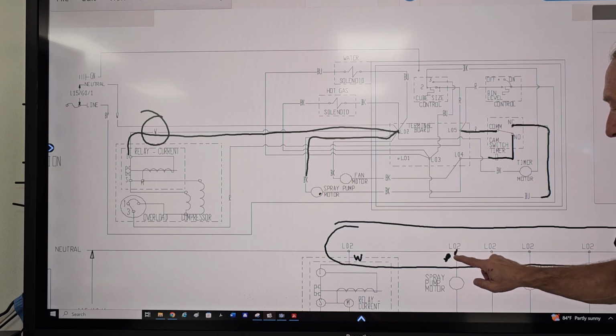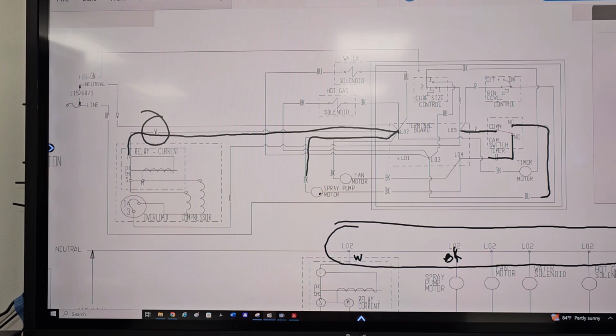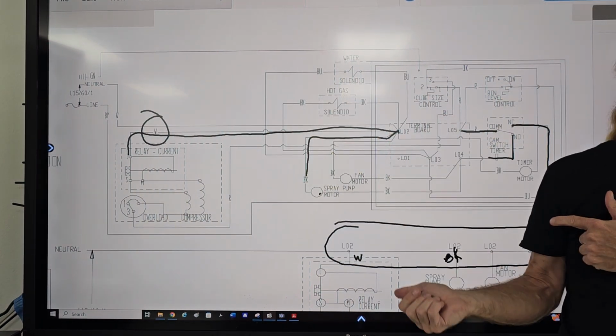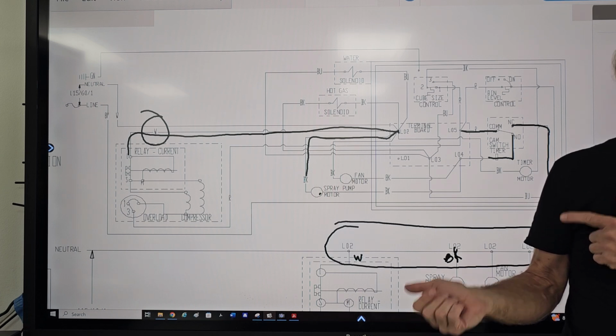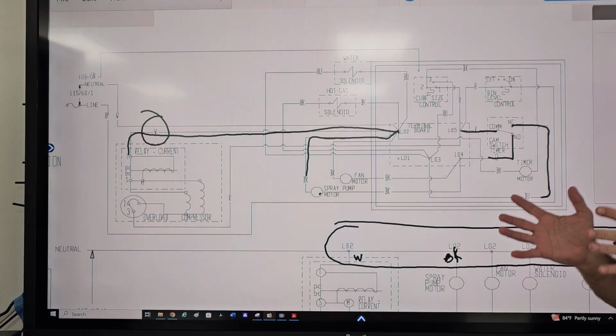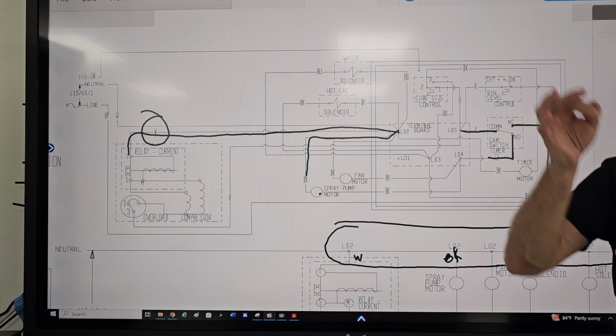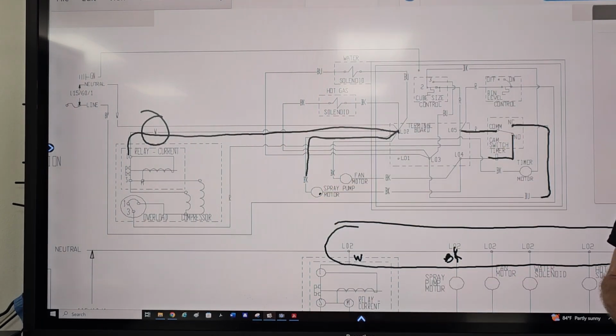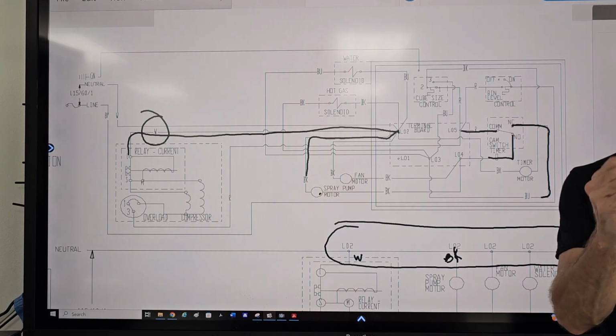If you can't read the diagram, you'd see a black and a white wire on the same terminal and think, wait, that's line one and neutral, it's going to short out. No, that's just the color. But you have to make sure, because there's more than one black wire, that the black wire connected to L02 is the right part. You know it's a black wire, but you have to confirm it.